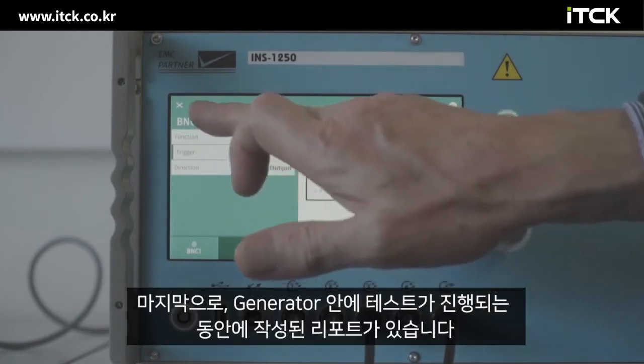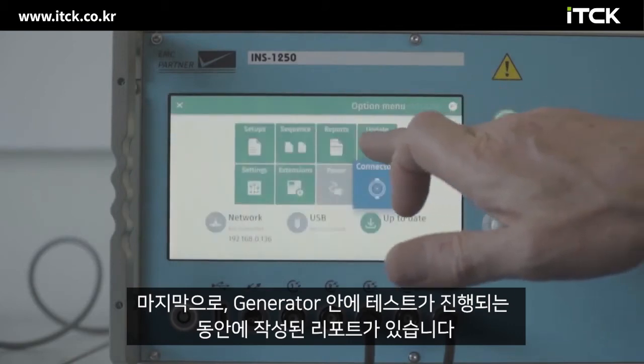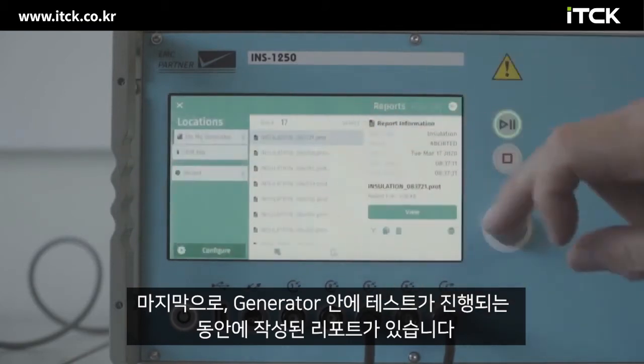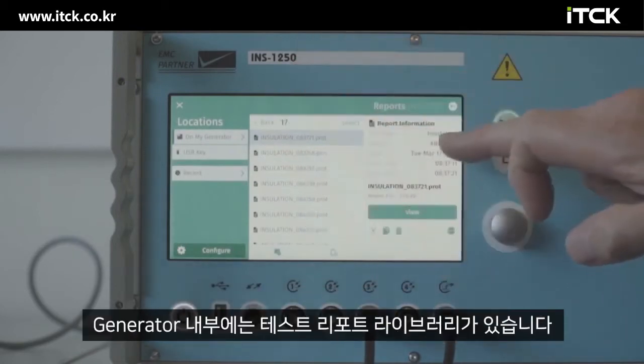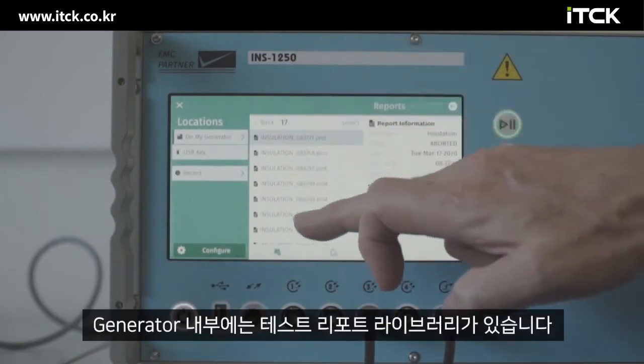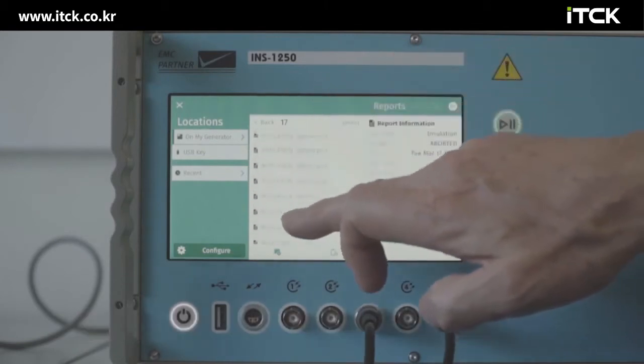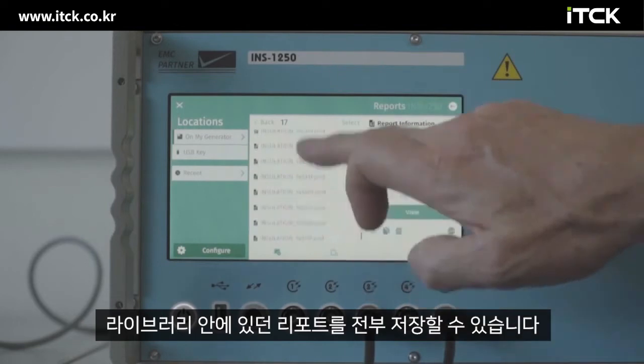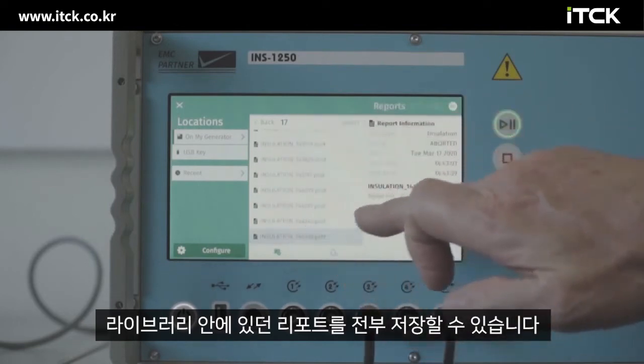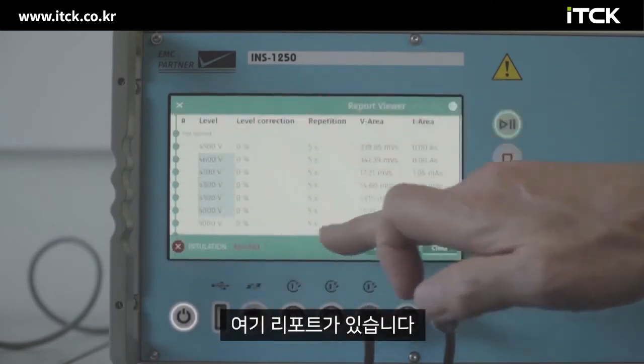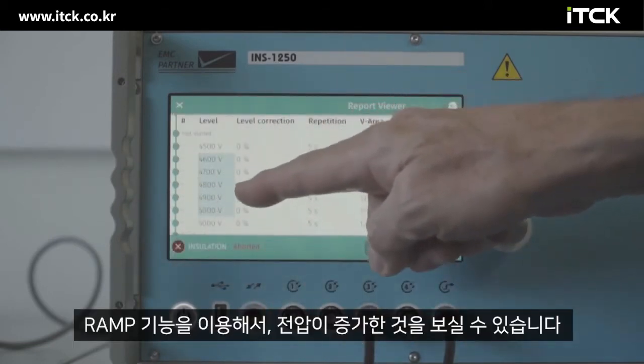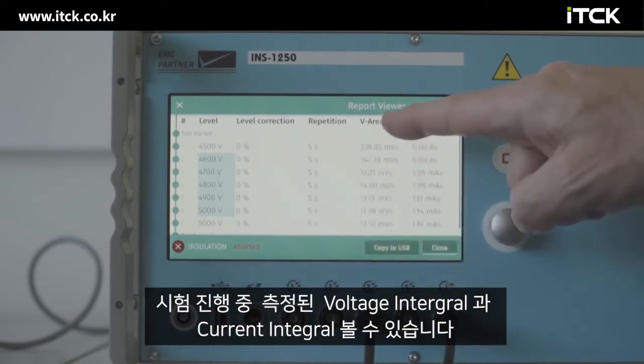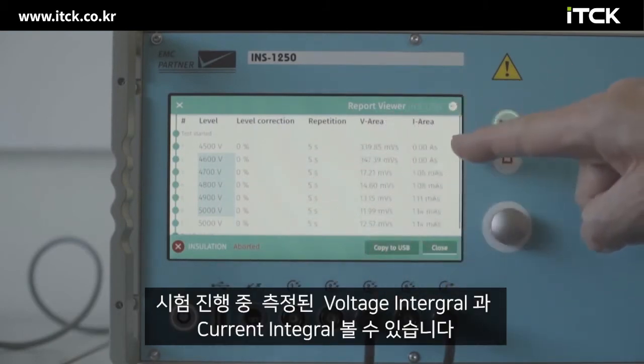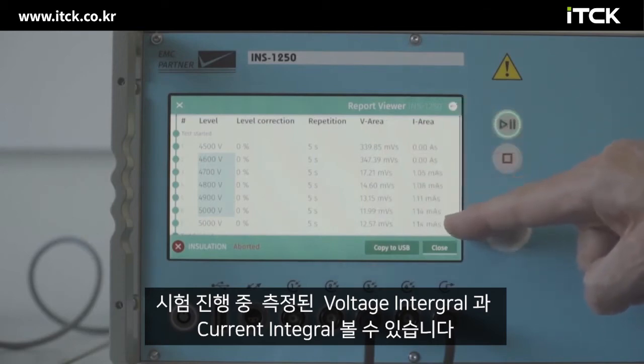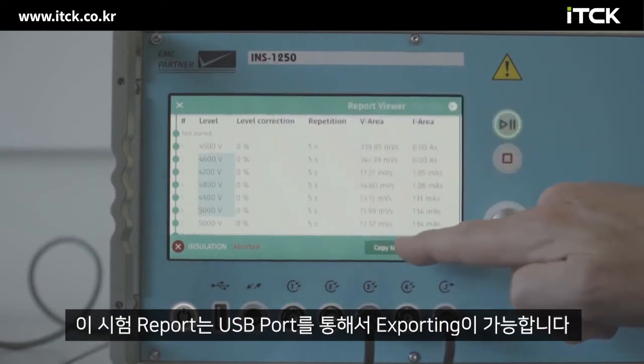Finally, in the generator we have the reports which are produced during the test processes. Inside the generator is a library of the test reports. We can store all of the reports that were taken within the library. Select, and we can view. So here is a report where the voltage was increasing using the ramp function, and we see the voltage integral and the current integral as the test progresses. This report can be exported from the generator through the USB port.